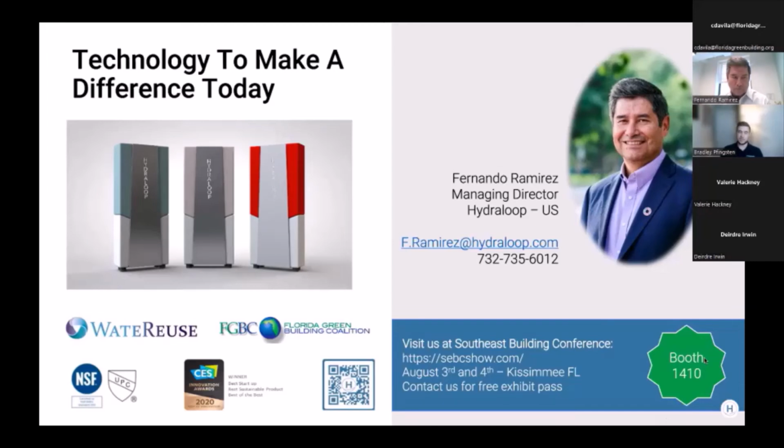The programming, I didn't really even touch on it, but the actual software that our R&D made themselves is connected to a mainframe network. I can monitor them, I can see them all, and they are smart enough to know if the Wi-Fi goes out for a certain amount of time, it'll dump the water. If the power comes back on, it'll dump the water because it doesn't know how good it is. So it actually has sensors, like with the UV, it has a sensor and everything. So there are automatic checks in this system that do cover those things. But regardless, we do recommend a UPS for it, especially being in Florida.